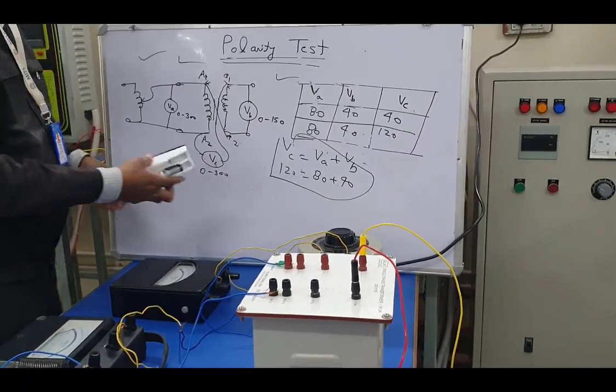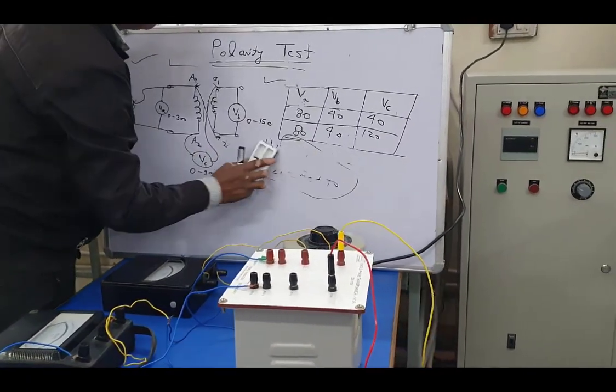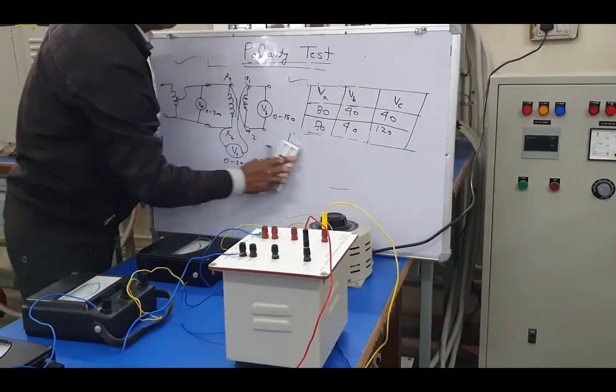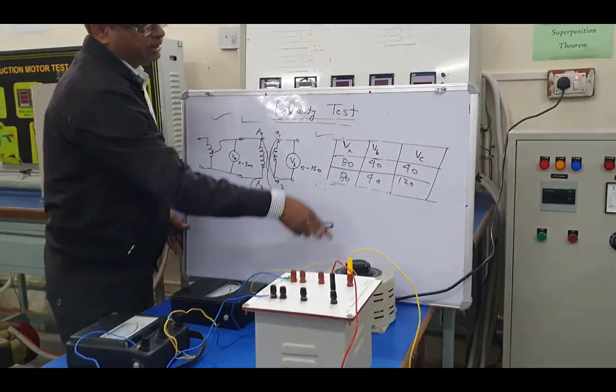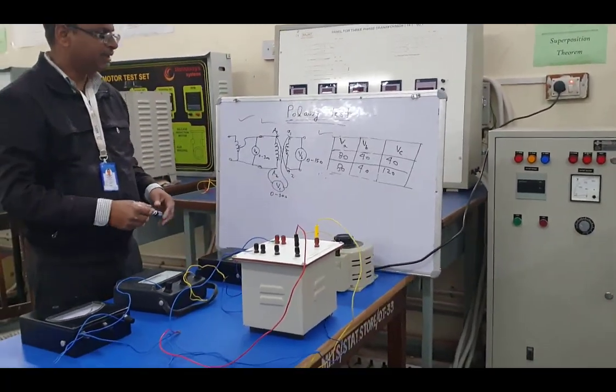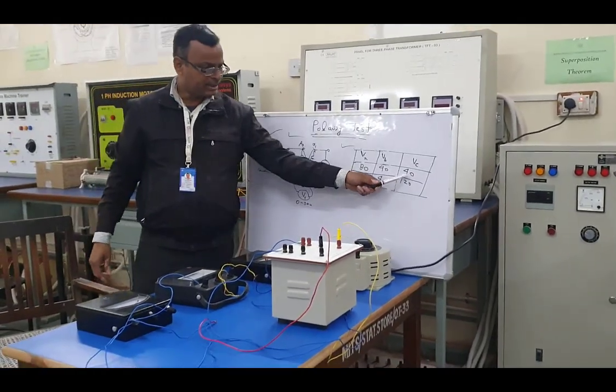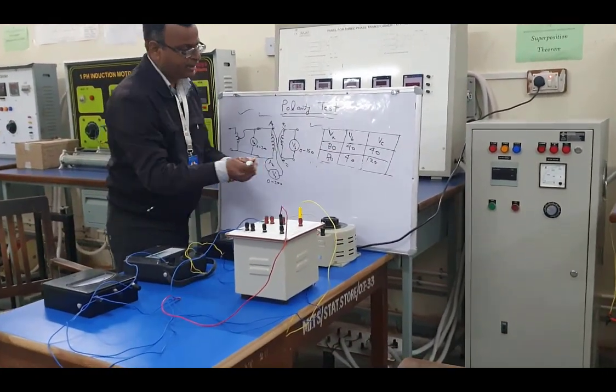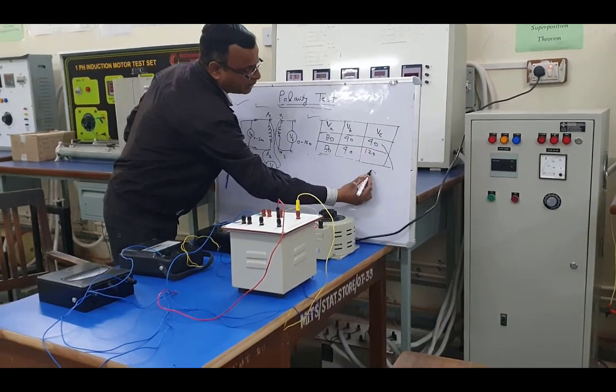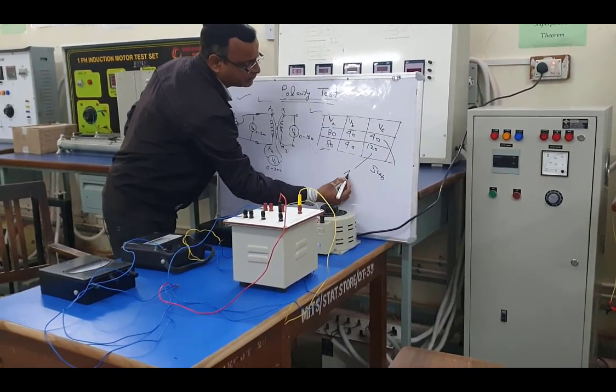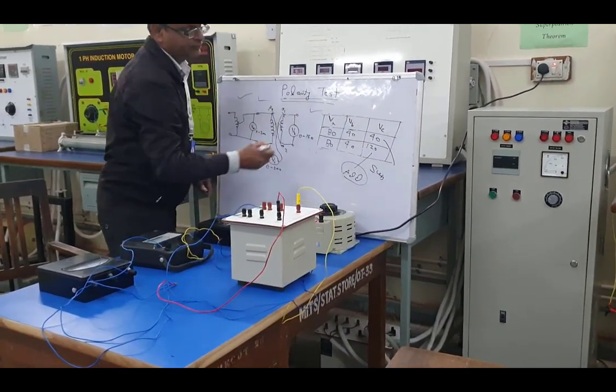And this polarity test is very useful in the case of parallel operation of the transformer. So these readings we have to put in our journals. One is the subtractive polarity, the first part, and this is the additive. This is the subtractive polarity and this is the additive polarity.